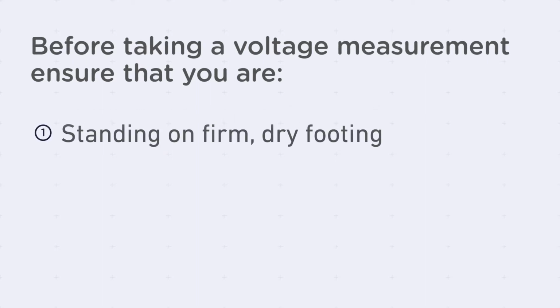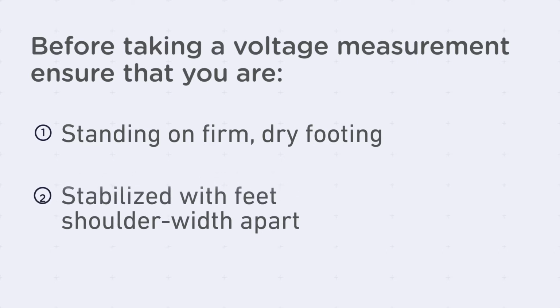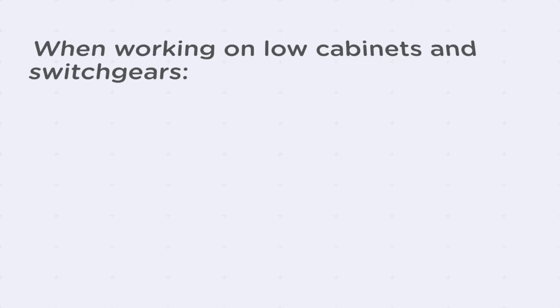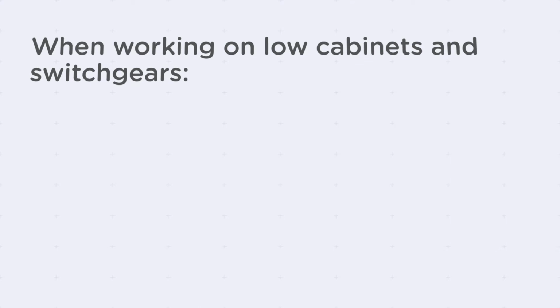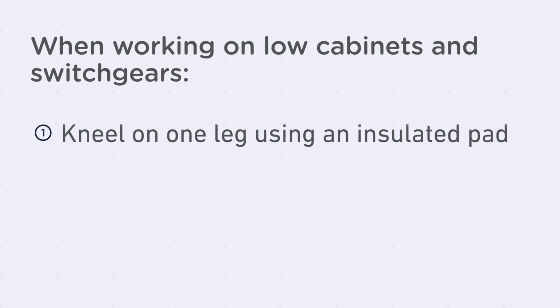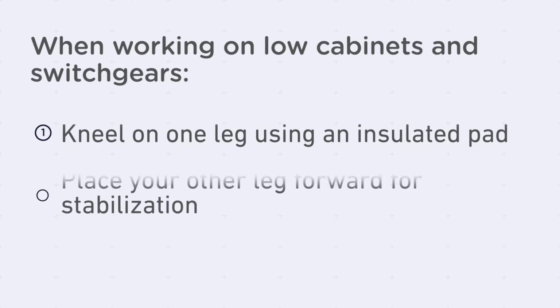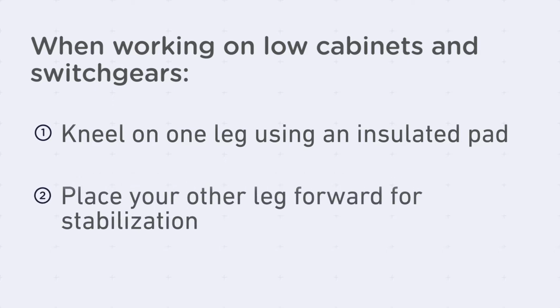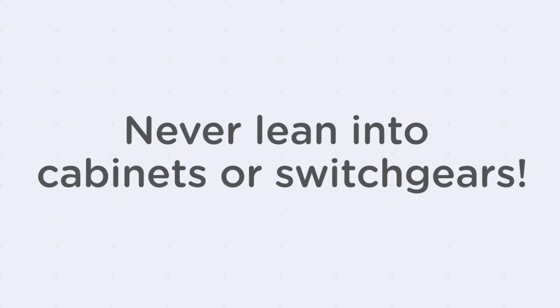1. Standing on firm, dry footing, and 2. You are stabilized with feet spaced shoulder-width apart. In the case of low cabinets or switch gears, kneel on one leg with the other foot forward to stabilize your position. Kneeling on one leg can only be done safely if an insulated pad is used under the knee. Otherwise, it defeats the insulation of the safety footwear. Remember never to lean forward into cabinets or switch gears.